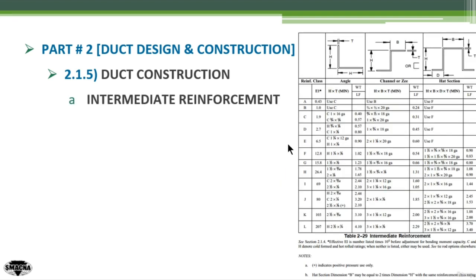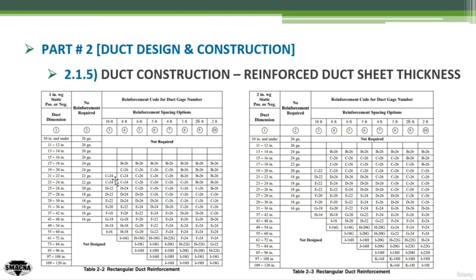Going to the following slide, you can see Table 2-29 giving the framing, angle, or channel details which were referred to in the previous slide. From this table you can obtain all the related details of the reinforcement requirement and all the physical dimensions. Based on the reinforcement class obtained from these tables of the rectangular duct classification — in tables starting from Table 2.1 or 2.2 onwards — you can see that these tables give you a reinforcement requirement indicated by a letter symbol. This letter denotes the reinforcement classification, along with the gauge of the duct required.